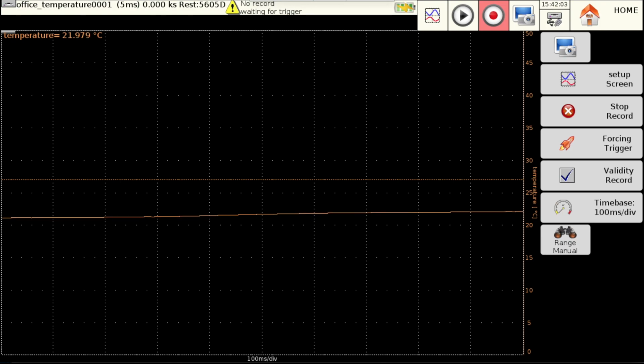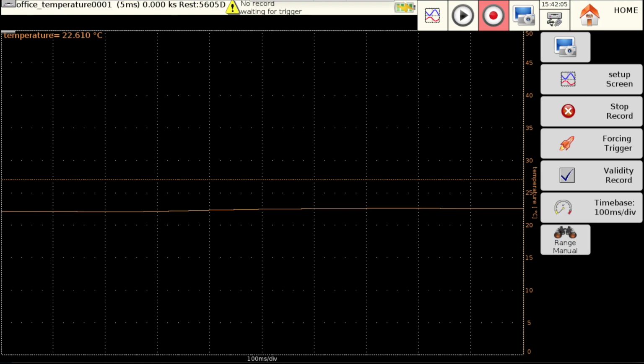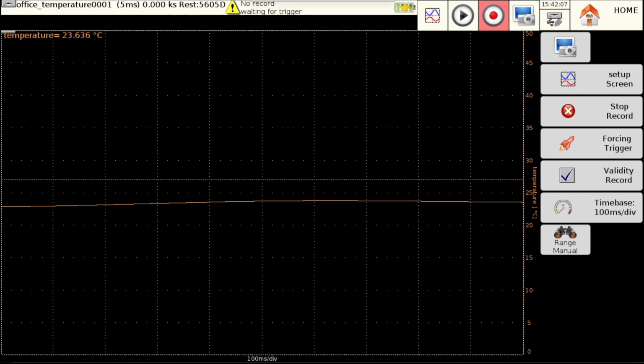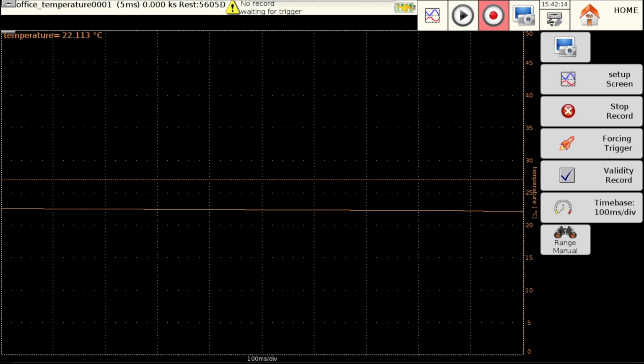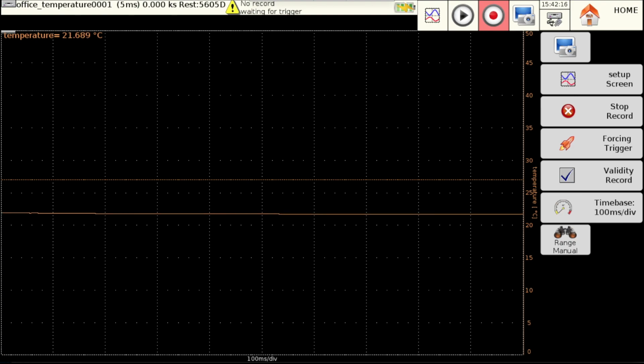Let's carry out our recording. The temperature rises and then stagnates and never reaches the threshold set previously. That means we have a problem with the parameters of our recording. The threshold value is now high compared with the actual signal. Let's fix that.